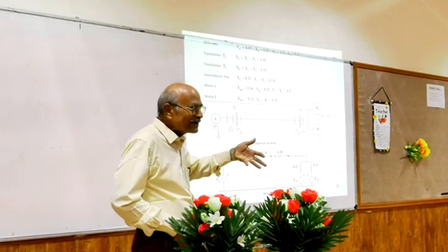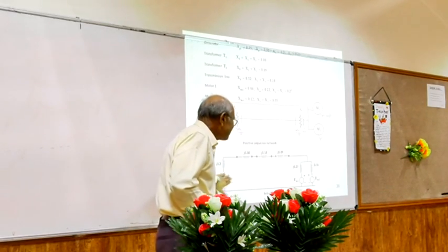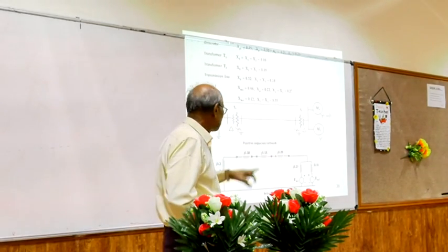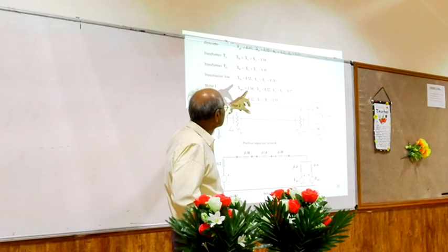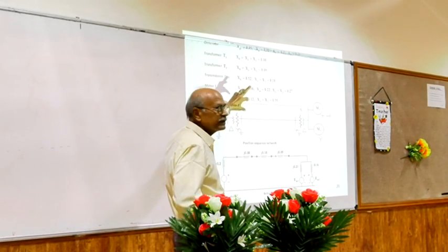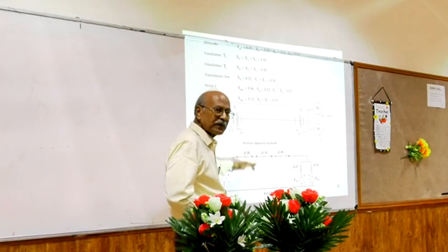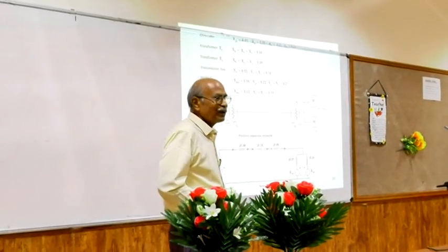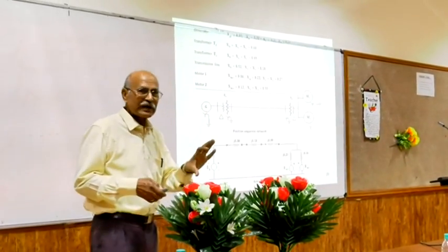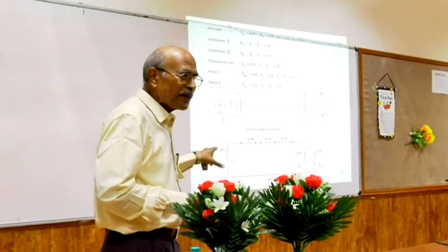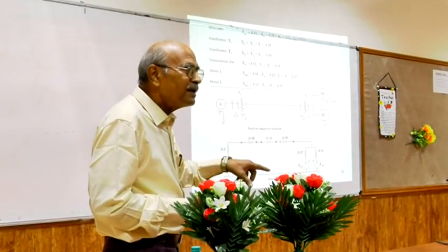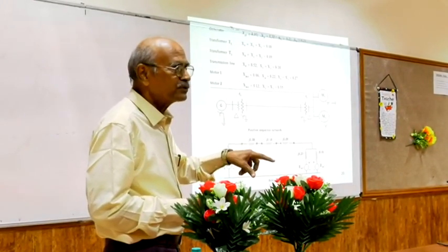So how is it going to be for negative sequence? No voltage sources will be there, number one. Number two, the positive sequence and negative sequence values may be different at some points. If that's the case, you properly change it, that's all. Only for zero sequence you need to be a little more careful. So always start with the positive sequence, then draw the negative sequence, then zero sequence.